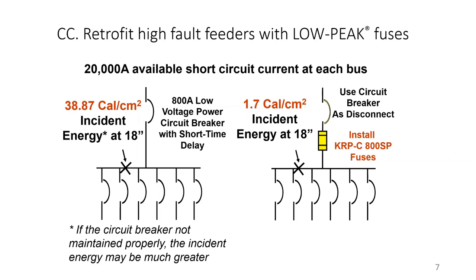So when you design a system, you have to look at those things as well. Look at reality. Where will the fault occur? Because I have a maximum available fault current of, let's say, 100,000 amps, doesn't mean that fuse will see that. And I don't think I have to mention this, all the engineers that I've taken courses from, people like Charles Pratt, Jim Phillips, the industry gurus, they always tell you that the most common fault will be a single line to ground fault, which is, of course, much, much less than the three-phase bolted fault current. And this is the challenge we face when we are analyzing a job.